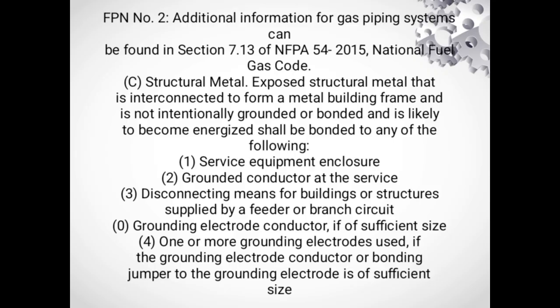Structural metal. Exposed structural metal that is interconnected to form a metal building frame and is not intentionally grounded or bonded and is likely to become energized shall be bonded to any of the following. Number 1. Service equipment enclosure. Number 2. Grounded conductor at the service. Number 3. Disconnecting means for building or structure supplied by a feeder or branch circuit. Grounding electrode conductor if of sufficient size. Number 4. One or more grounding electrodes used if the grounding electrode conductor or bonding jumper to the grounding electrode is of sufficient size.